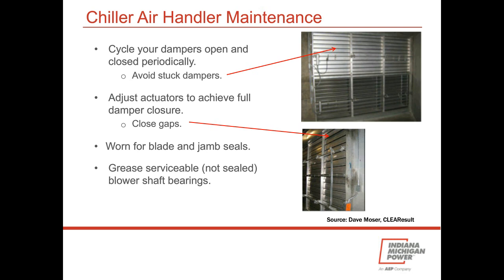Stuck dampers. Also, you can have a condition like down below where you have a slight opening in the quote-unquote closed return air dampers, and a slight opening translates to a pretty significant amount of airflow. So you have to verify that they close, and hopefully you have jamb seals that help as well. And so it's just important to check to see that what your control system is telling you is actually happening out there.